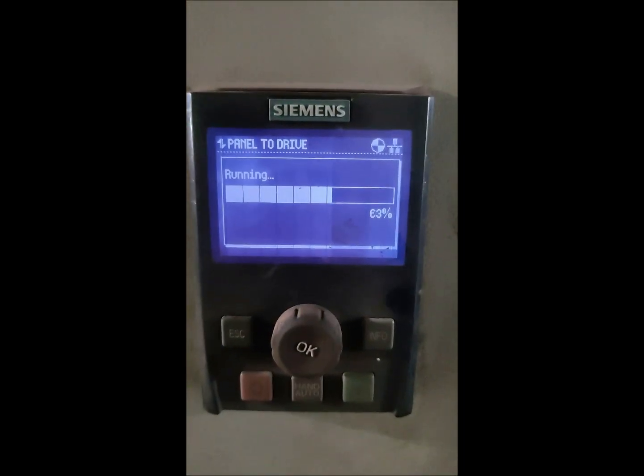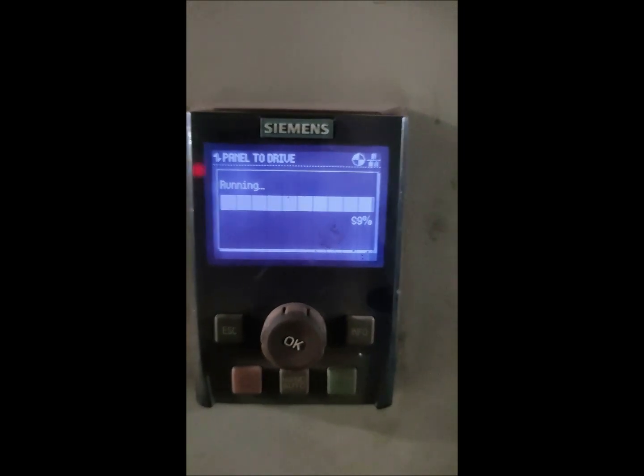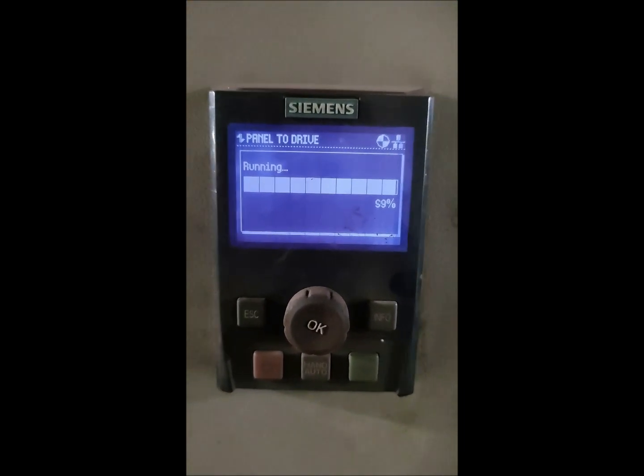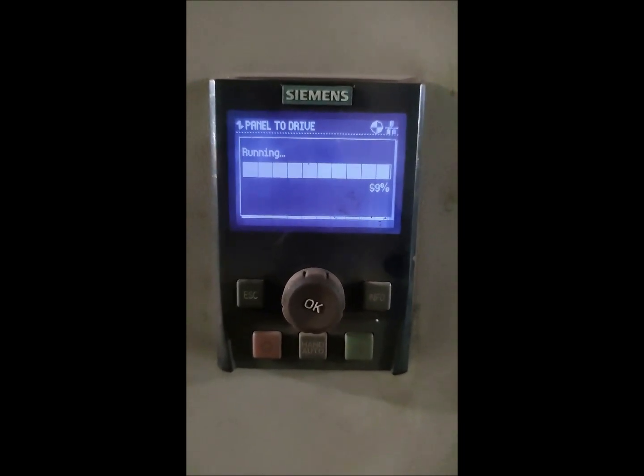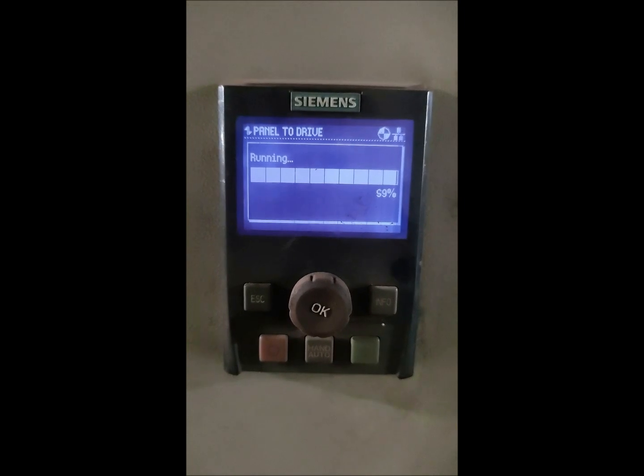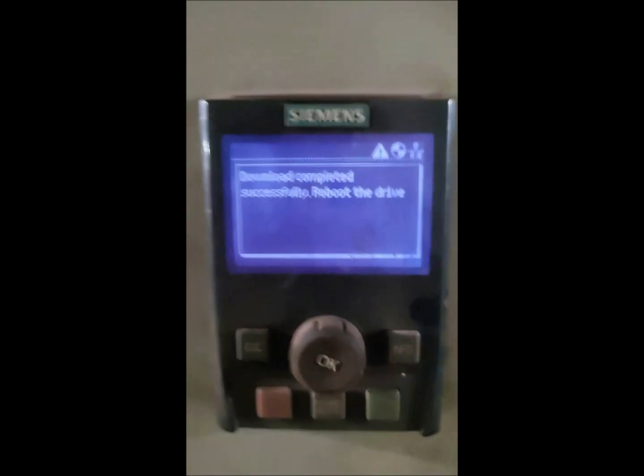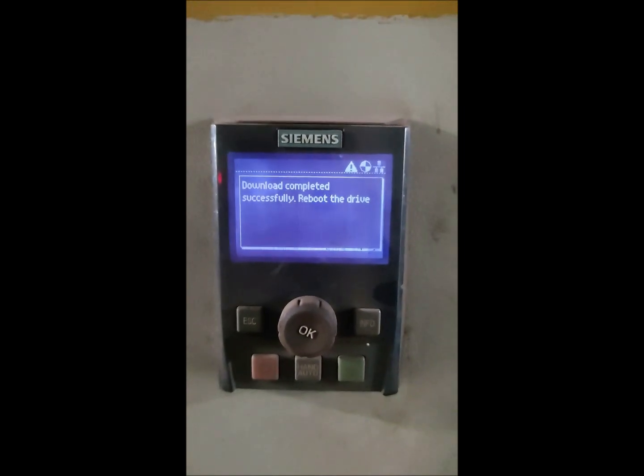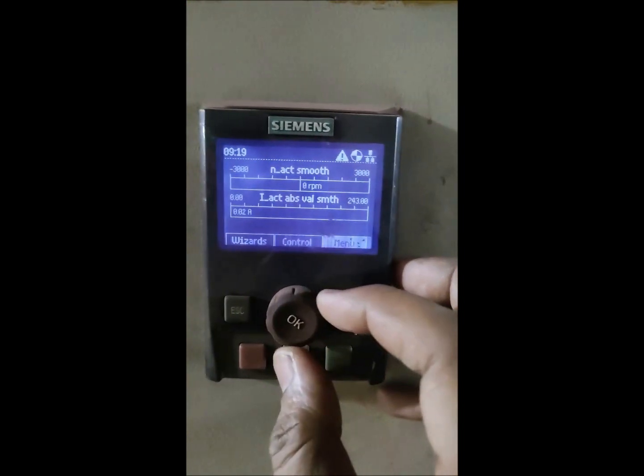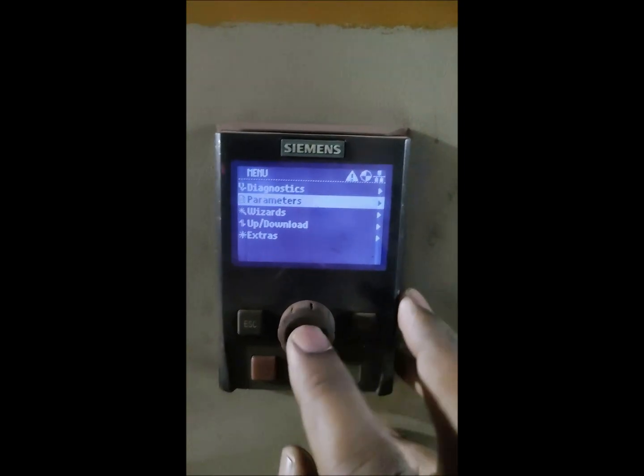And one thing you will observe: when the drive reaches 99% of the download, there will be two sounds coming from the power contactor - on and off - and the drive will still be in faulty condition. So at this point at 99% you will observe this sound. Now the drive has been downloaded - the program has been downloaded successfully. Next we have to reboot the drive, that is switch on and off, and later on we will go back to the menu to check whether the program has actually been downloaded or not.